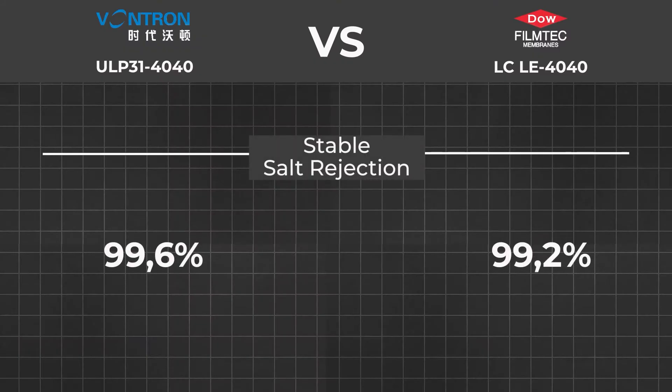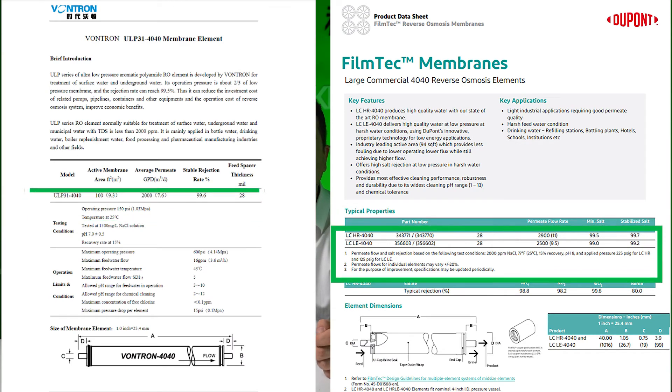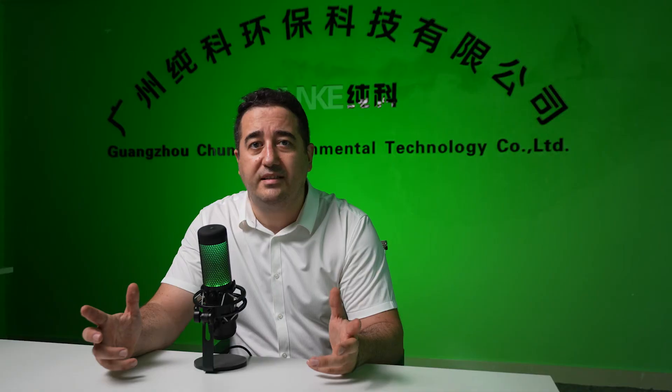Stable salt rejection: from the table, Vontron membrane salt rejection is higher than FilmTec — Vontron is 99.6% and FilmTec is 99.2%. However, the test conditions are not exactly the same, so as a user it is difficult to compare them fairly. Salt rejection is an important parameter for choosing a membrane, and we suggest Vontron apply the same test conditions as FilmTec. Minimum salt rejection: FilmTec shows a minimum salt rejection of 99% in their specification, but we cannot see this value in Vontron's specification — Vontron, please provide more data on this.